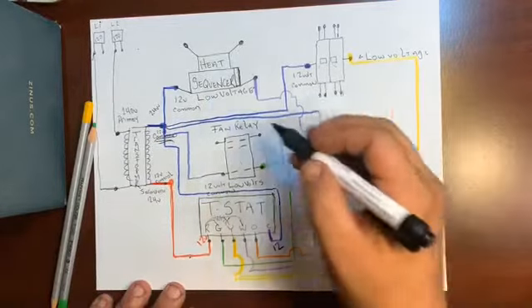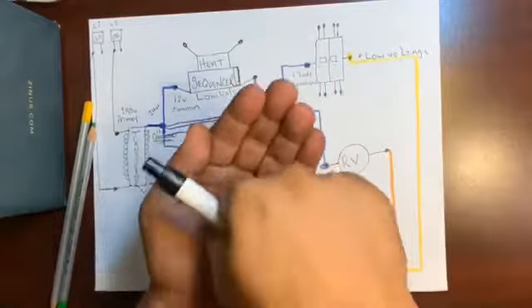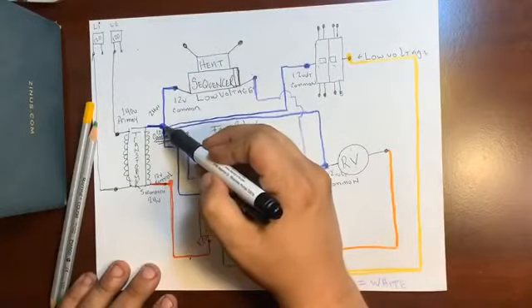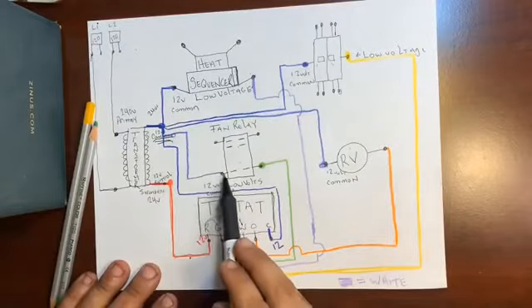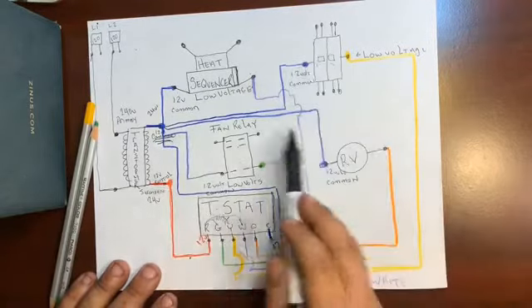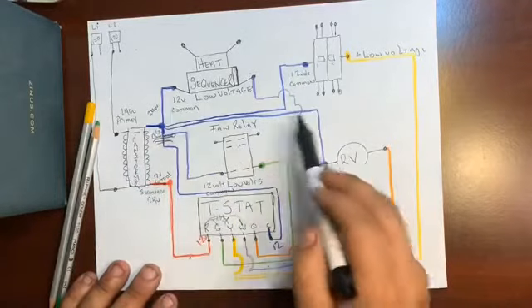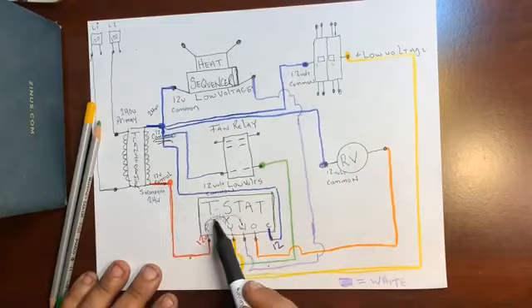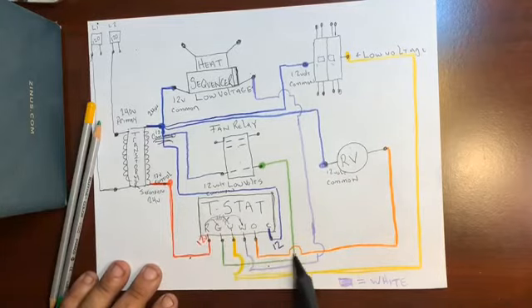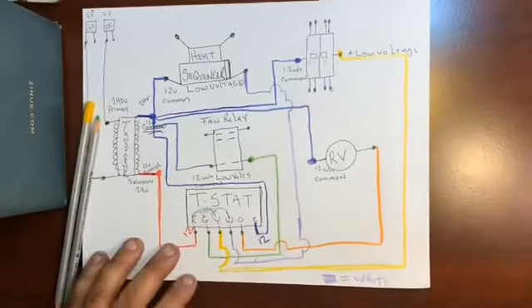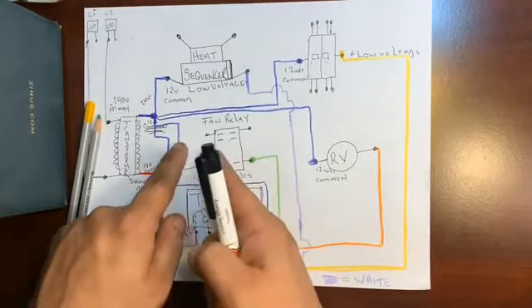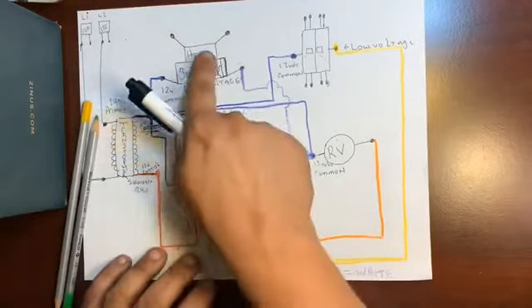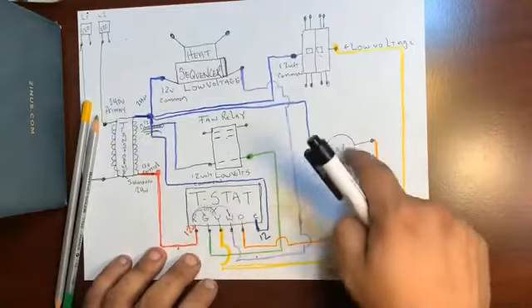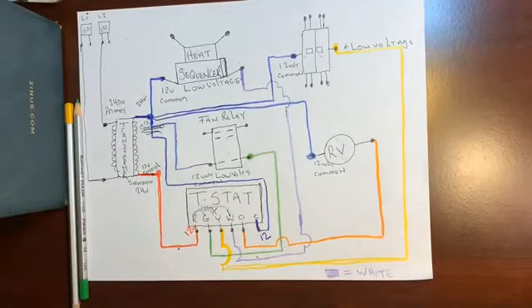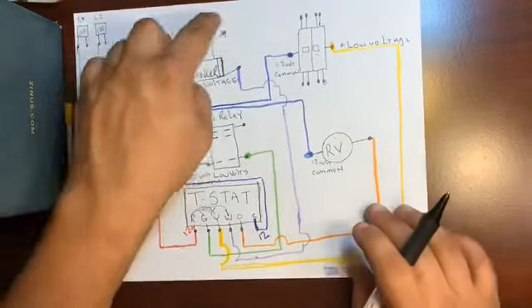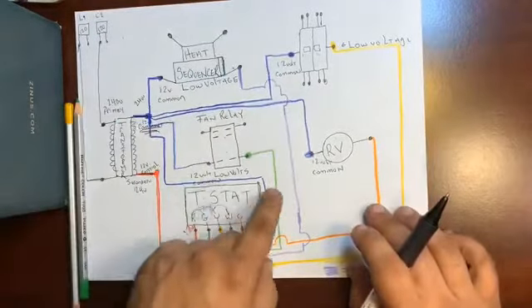From there, the relays each say to the transformer, put the common in my hand. And the common will leave the common side 12 volts, feed half of the heat sequencer, half of the fan relay, half of the contactor, half of the reversing valve. These blue wires never go away. It's only the control, the other 12 volts, that is manipulated by the thermostat to give it the other 12 volts for it to start, for it to close. What a relay does is it takes low voltage and then it opens a channel, either to turn on a fan relay, to turn on heat strips, to turn on the compressor, to engage a reversing valve. That's what low voltage is. It's us controlling high voltage with just 12 volts of low voltage through a thermostat.